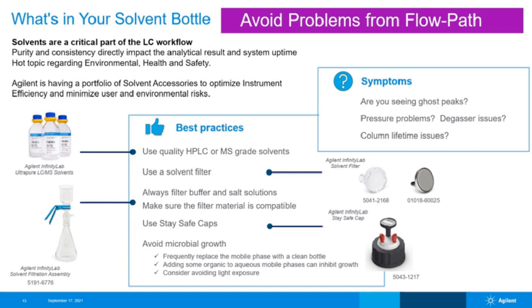Definitely use HPLC or even MS-grade solvents, depending on your sensitivity requirement. Use clean glassware. Rinse it with a bit of mobile phase before you fill it up. You can use a solvent inline filter to catch larger debris or dust that might happen to be in your bottles. But there is no substitute for good, clean lab practices here. If you are using any buffer or salt solutions, it's a good idea to filter your mobile phase, but be sure the filter membrane material is compatible with your solvent.